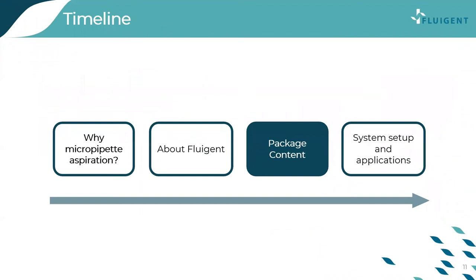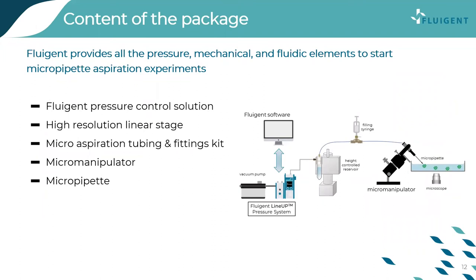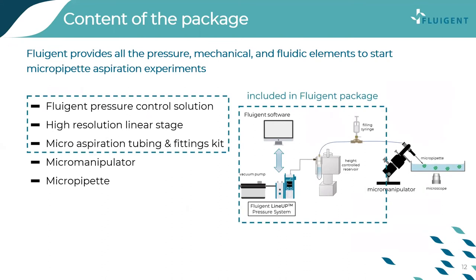Now that we've covered the advantages of micropipette aspiration and introduced our company, let's look at the package content. The micropipette aspiration setup consists of a microfluidic flow controller, reservoir and high-resolution linear stage, tubing and fluidics to connect the reservoir to the micromanipulator, and a microscope for live visualization. The package provides all pressure, mechanical, and fluidic elements to start micropipette aspiration. We also researched and can suggest the ideal micromanipulator and micropipettes.